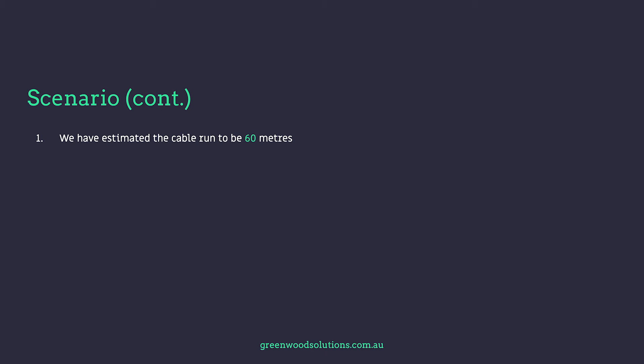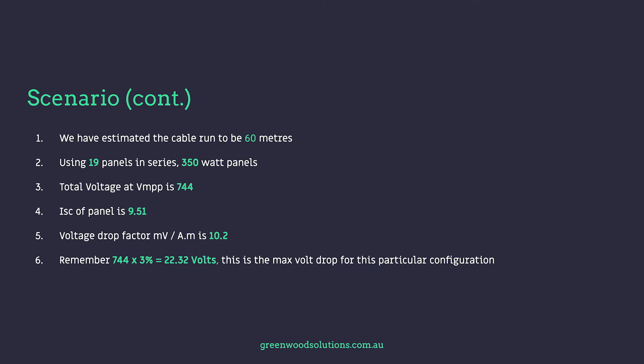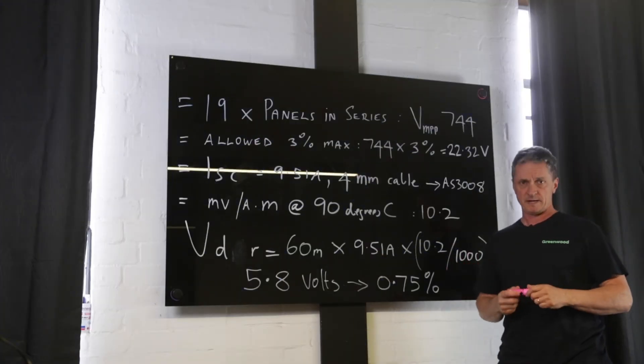We've estimated the run at 60 metres, using 19 panels in series, a voltage at maximum power point of 744 volts, a short circuit current of 9.51 amps, and a millivolt per amp metre Volt Drop of 10.2. That gives us 22.32 volts to play with — 744 times 3%. It's very important to go through the process to understand what you're doing, then check your results with one of the many online calculators available for DC Volt Drop.